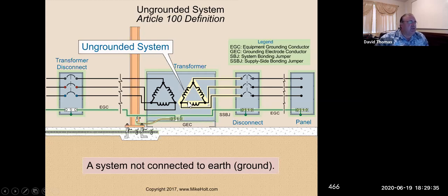Nothing would happen. This is kind of why the Europeans like their ungrounded systems, because it's safer. But that's only if we did have a fault detector, something that actually told me that something went to ground. That would be the only way you would know if something went to Earth or to the equipment ground. Because if you grab, let's say, a second wire, if you do touch another wire in the system, now you've completed the path. If you are standing on something that's energized, you are going to have current go back into the system, but you're becoming that path instead of the bonding jumper between the equipment ground and the system. It's called the main bonding jumper, or the system bonding jumper, SBJ. Then you're becoming the system bonding jumper. Okay, so.